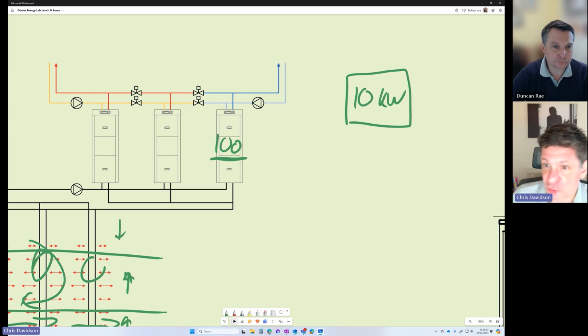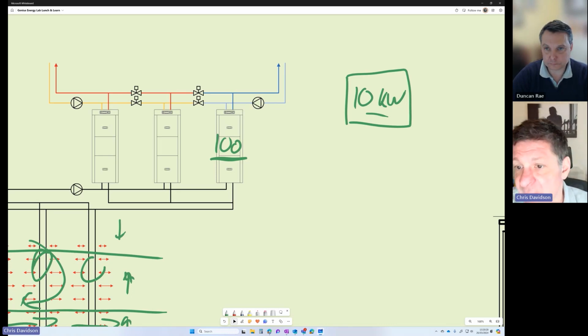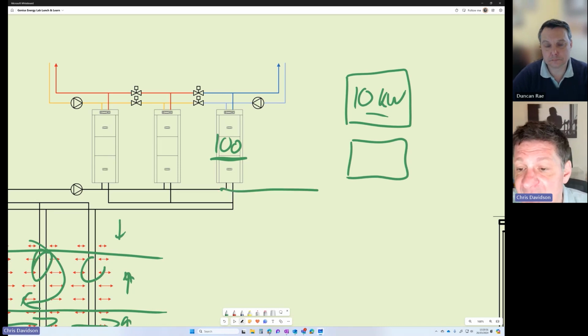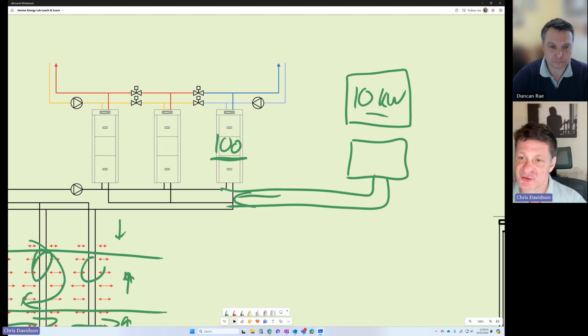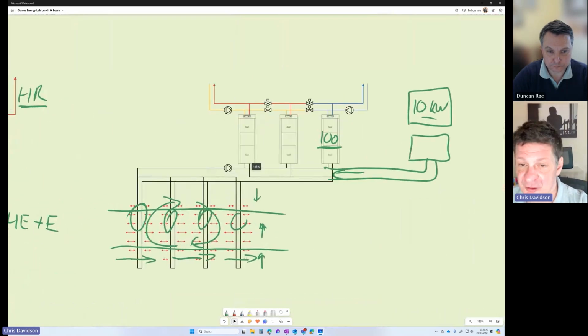Now, think of that as you're driving forward in your car, and you're now reversing it and accelerating violently in reverse. It's not going to be good for either fuel economy or the longevity of your car. Exactly the same is true for a heat pump. If you're reversing, then turning on that big heat pump to satisfy that relatively small load, it's not going to be either efficient or good for the longevity of that heat pump. So once you understand you've got that 10 kilowatt cooling load all year round, you might just dedicate a little heat pump to it, connect it up to the ground loop so it's injecting heat back in, and that's just going to look after that 10 kilowatt server room load all year round. So that illustrates the type of considerations that you've got to go through when you're looking at the geology, the heat pump selection, and how you deliver that into a building.